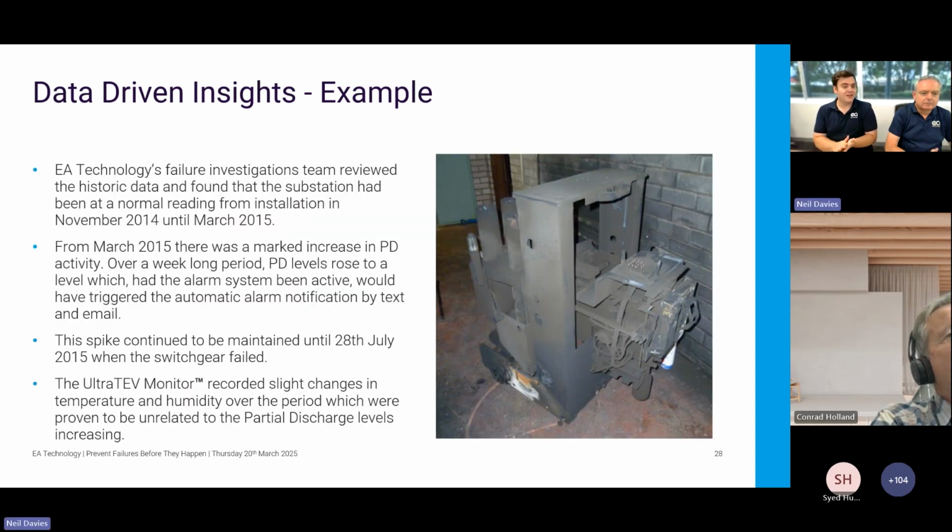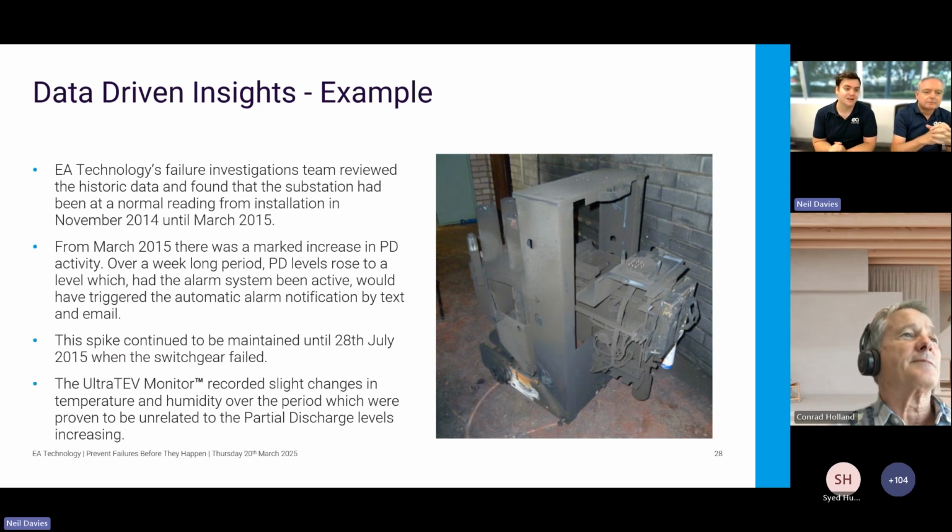When we initially went to site, there were no defects. They did a scan, they installed the board. However, 4 months later, they did have a failure on one of those circuit breakers. It was detected by the system, an alarm did trigger, but they failed on the one critical component where there was no communications set up between the monitoring system and the engineers. So there was no notification sent out, and no action was taken.